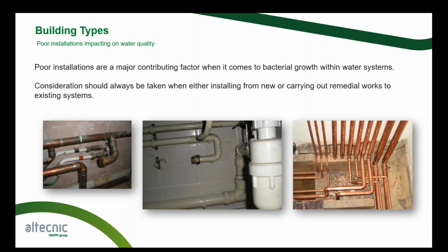So we've got a couple of examples here of where we are putting potential risk into the water systems. We can see here we have some capped off areas, whether it be under a basin, which looks like where this was taken from, or a run of pipe here. They're just capped off, so there's going to be no water flow.